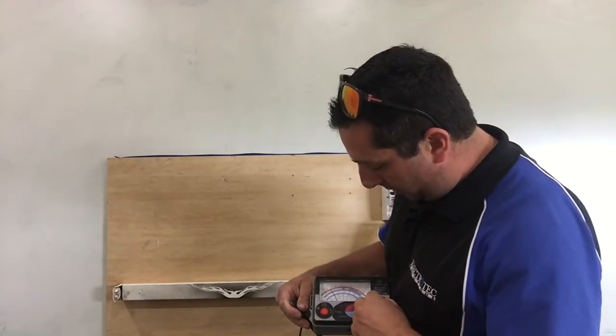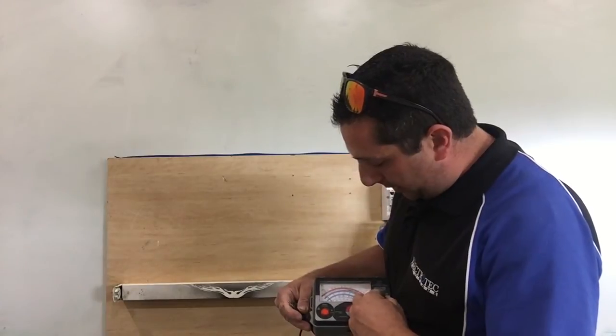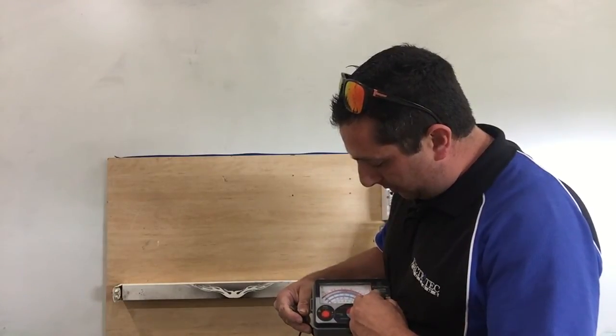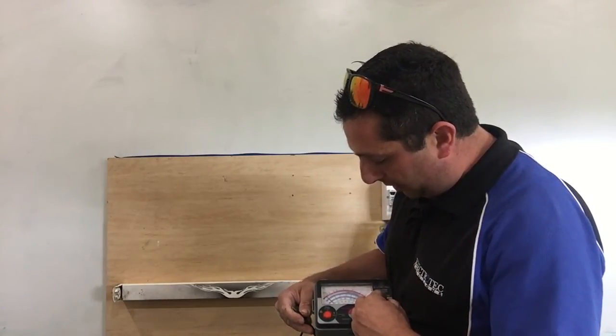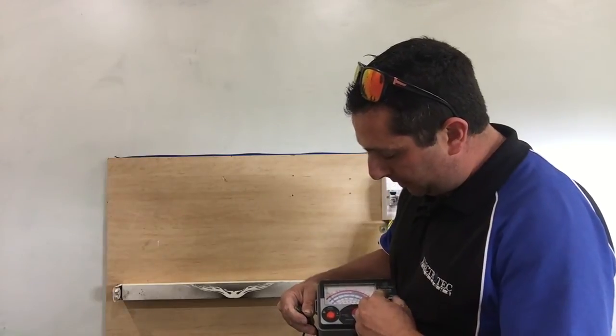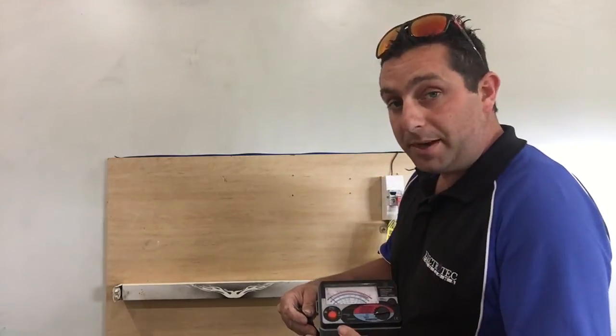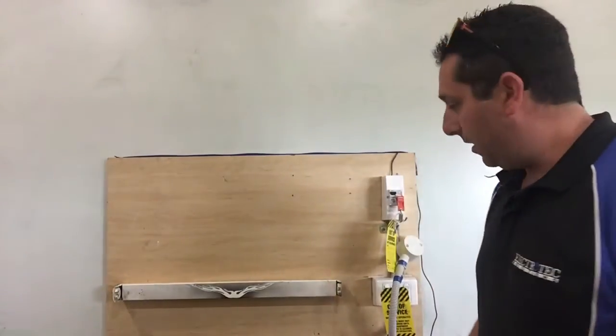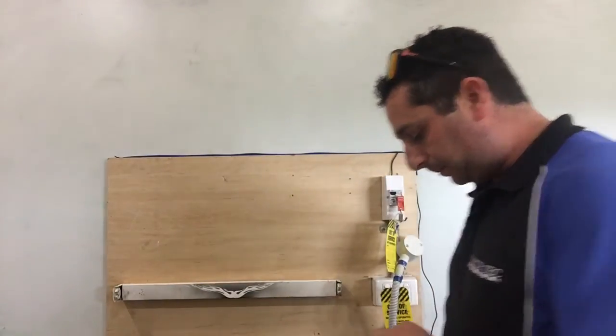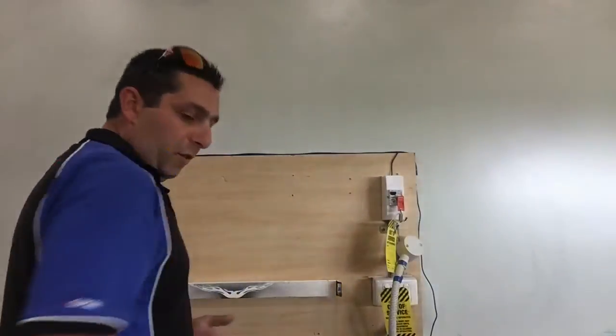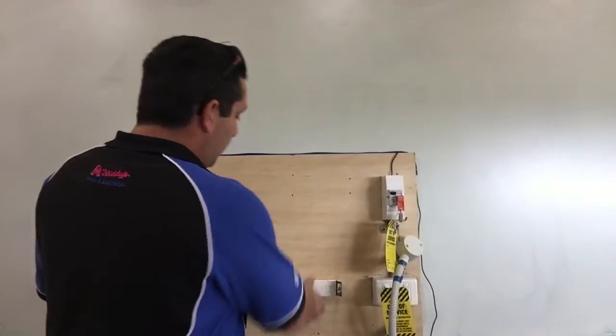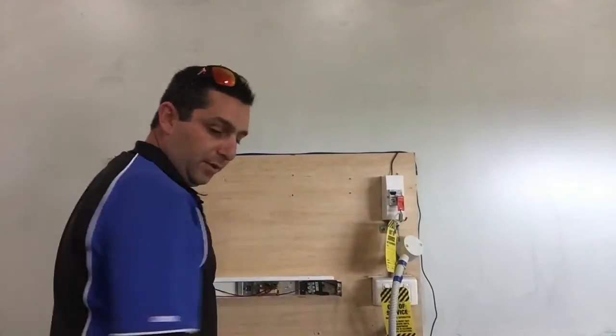Now this is quite a way off. We're going to get that down to 0. Looking at it the way I am is not exactly correct. You want to be directly over the top of the meter, looking straight down at it so that we don't get any variance. So I'll just pop that down to the table and have a look, and I've got that exactly down to 0, so I'm well happy with that. Alright, on our 500 volt scale, we're going to do an insulation resistance test on the appliance.